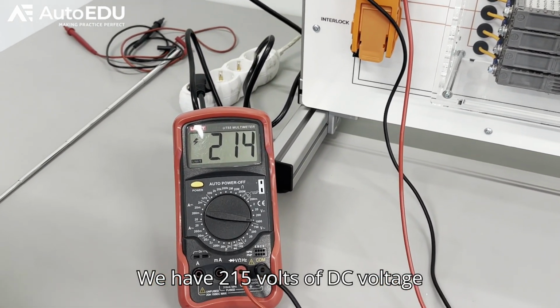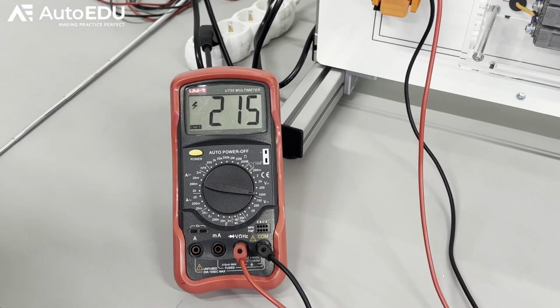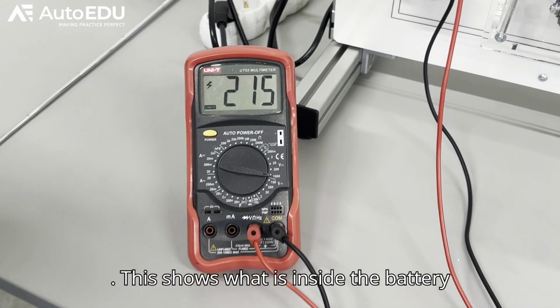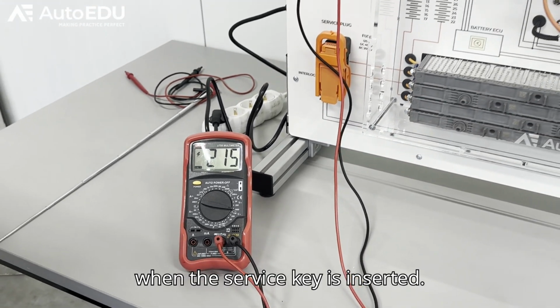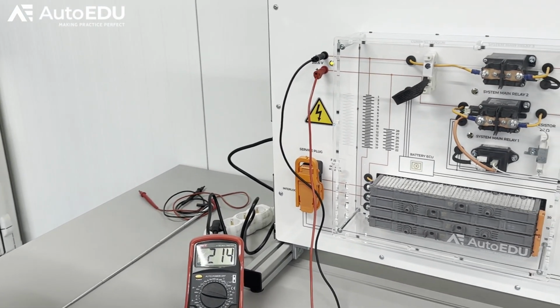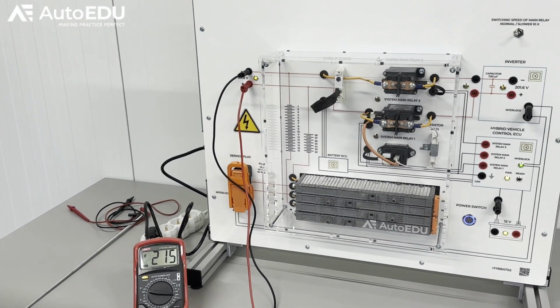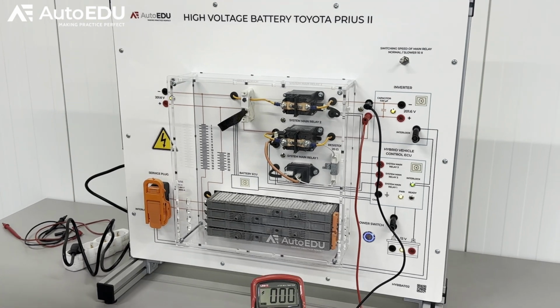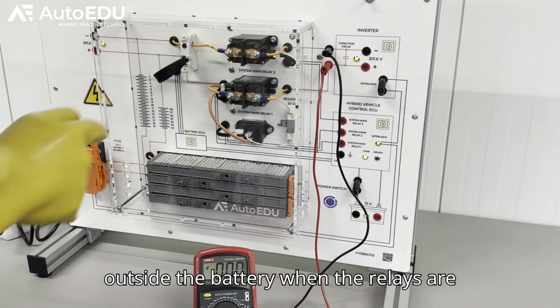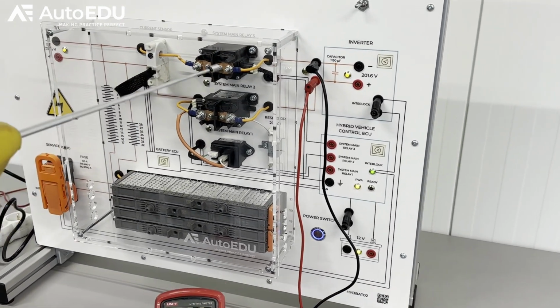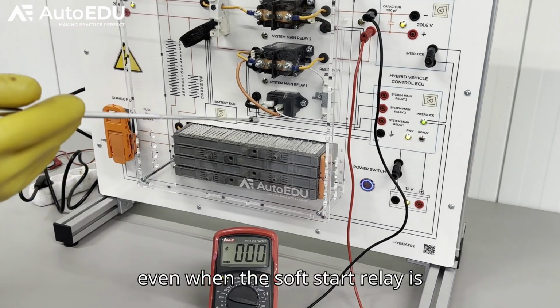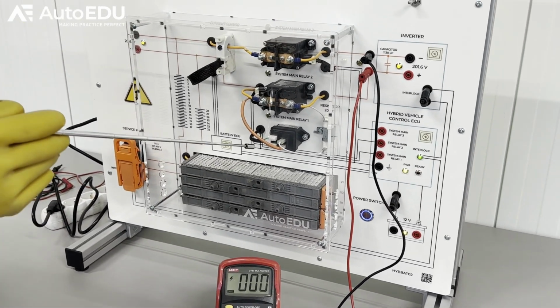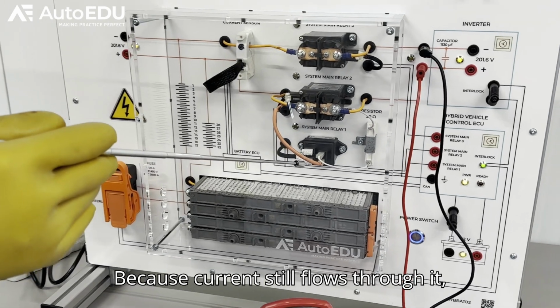We have 215 volts of DC voltage. So, this shows what is inside the battery when the service key is inserted. Now, we'll show how high voltage appears outside the battery when the relays are connected, and voltage appears even when the soft start relay is activated, because current still flows through it.